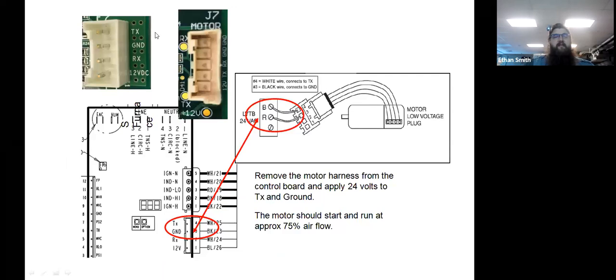Okay, so the board, you'll have a plug that looks like that. It's a four pin or 5-pin harness, depending on what your equipment is. And we're going to apply power to TX and ground. So you can see on these motors, we've got TX and ground here. And over here, we've got TX and ground. So this plug here is actually this guy right here. Okay, we apply 24 volts to that, and the motor should start at about 75% airflow.